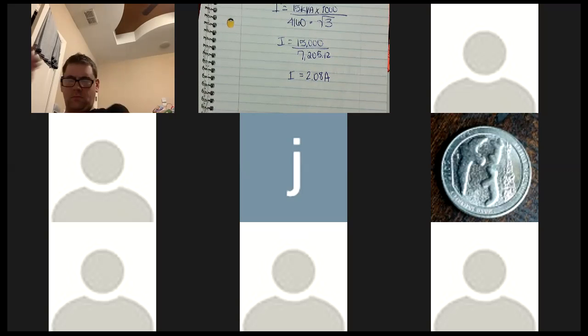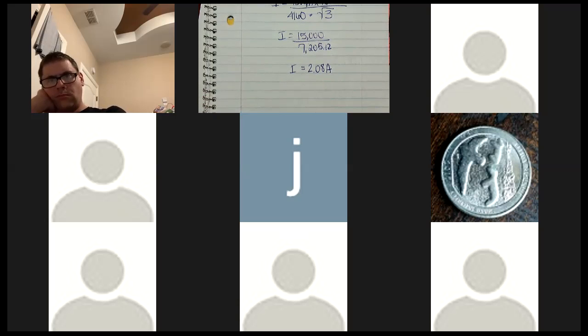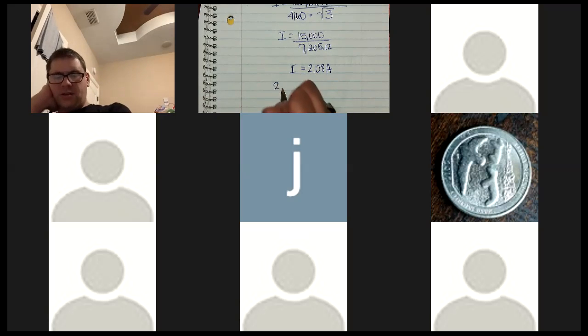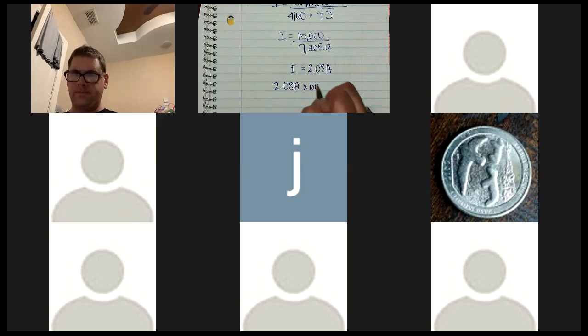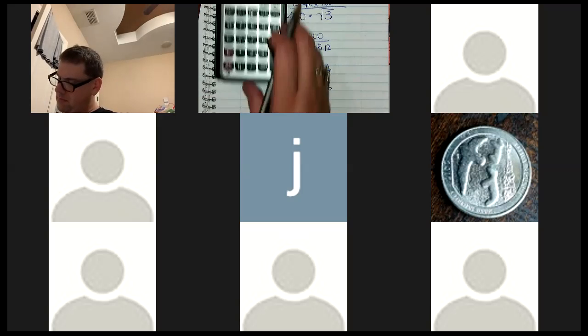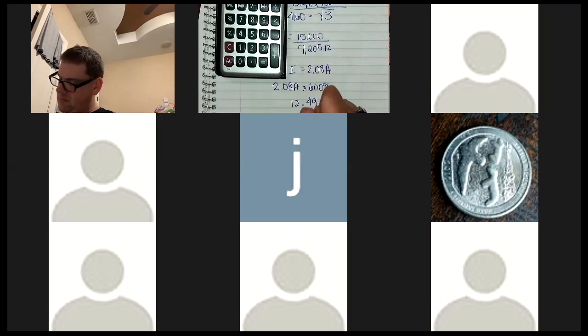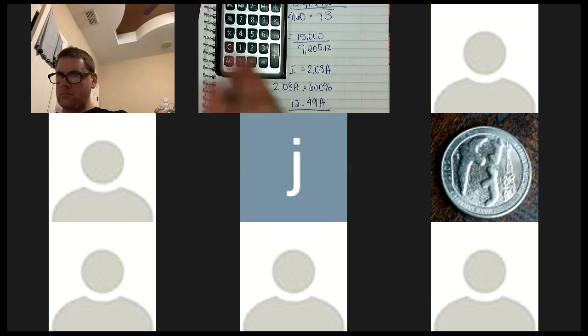Okay. I feel like I'm forgetting a step. No, I'm not. Okay. So we have 2.08 amps, right? Now I have to rate it. And when we were looking at the chart, we determined that it was going to be what? The 600? So right here, amps times 600%, right? Times 6.00. I end up with 12.49 amps, right?